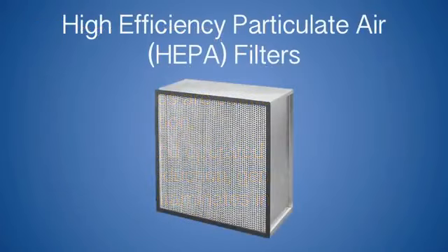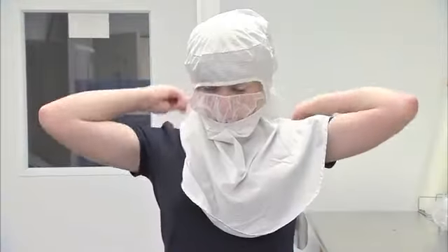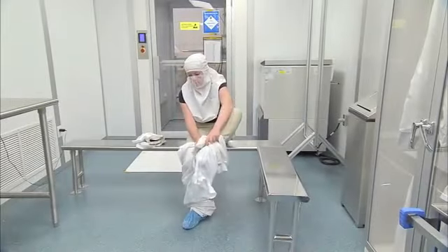Filtered air flows into the room through high-efficiency particulate air, or HEPA filters. Clean rooms are classified based on the amount of allowed airborne particles in the room at any given time. The fewer particles allowed, the more precautions that must be taken in order to prevent contamination.